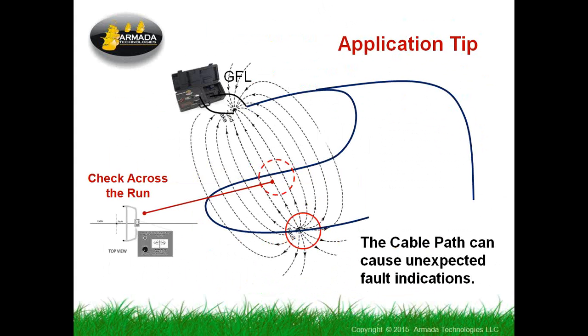You can double check for false indications like that by doing the cross check across the run. It's the same thing that gives us the really tight indication about the location of the fault. If you cannot do a triangulation on the fault across the cable, you are in a false location and you need to keep going. Generally, the rule of thumb is when you are getting goofy indications, you're not sure, it seems to be pinging in the wrong direction or the signal has gone away, you just need to keep going. So always keep going. When you get close to the place where the fault has occurred, you'll start getting indications that make a whole lot more sense and you realize you're on top of it. Then you do your cross check across the wire and compare it with your lateral and you'll get a good find.